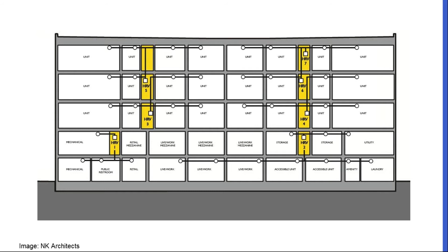What we're able to do, because the units are very small, we're able to use the ventilation system itself. We had six doors going simultaneously in the building, using the ventilation to do it, pulling out the cores of the Zehnders and checking all of them to make sure we have the same pressure at various locations, all interconnected. So we only needed 6 doors instead of 30.